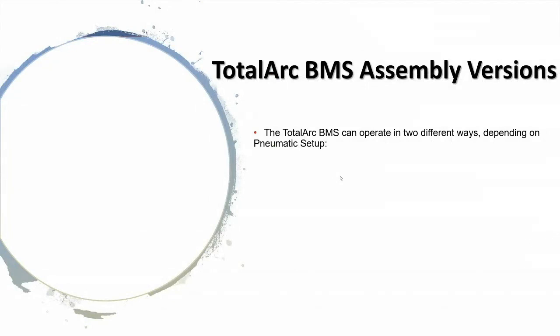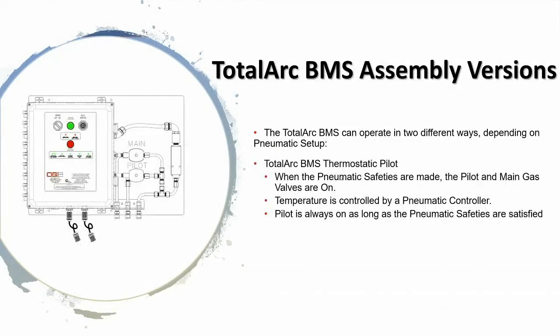Given that we can operate this unit in two different ways, we're going to discuss the pneumatic system, the most simple approach to this TotalArc. On the thermostatic pilot, when your safeties are on, your pilot gas is going to be on at all times. Your temperature control is actually controlled by a pneumatic controller. Pilot is always on as long as your safeties are okay. This would be more oriented to units that have more thermal mass on their bath.